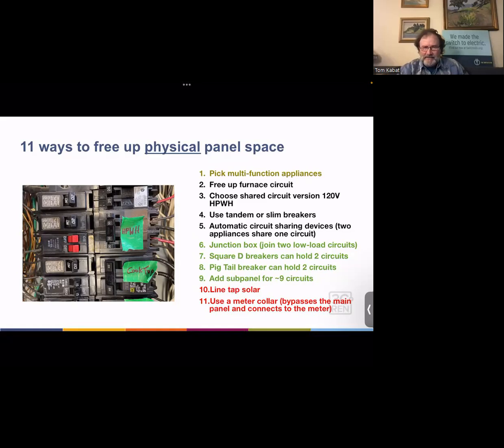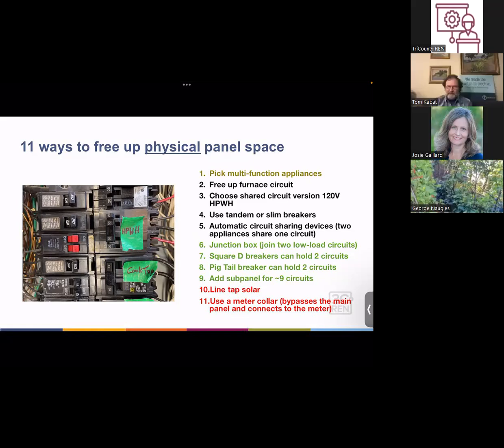Then there's the option of just adding a sub panel, which really lets you add a bunch more circuits. Maybe if you had a 10 circuit sub panel that takes 1 circuit to power, then you've added 9 net circuit spaces. And then the two red items at the bottom are for when you're adding solar - you don't have to add it through a circuit breaker. You could use what they call line tap solar, where it just joins into a power line between the meter and the panel, or the other is using a meter collar.